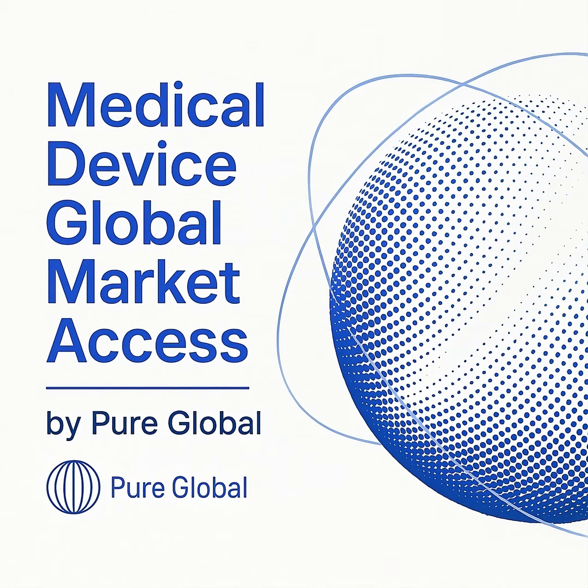For mechanical performance, the FDA recommends a suite of tests, referencing consensus standards like ISO 8637. This includes evaluating tensile strength of the tubing and connectors, security of connections under pressure, leakage, flow rate accuracy, and resistance to kinking. The goal is to prove the device can withstand the mechanical stresses of a typical hemodialysis procedure without failure. Beyond mechanical integrity, the guidance places strong emphasis on biocompatibility and chemical characterization.